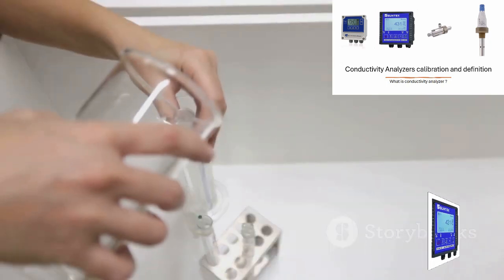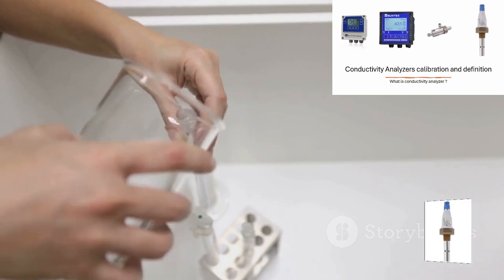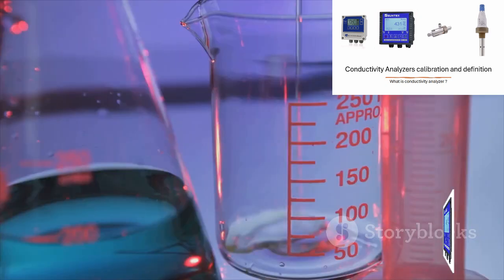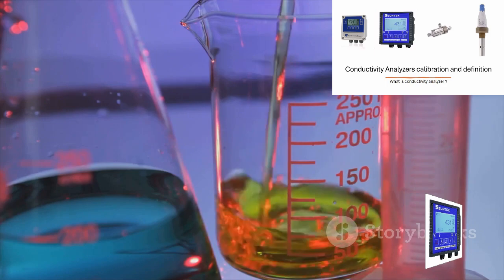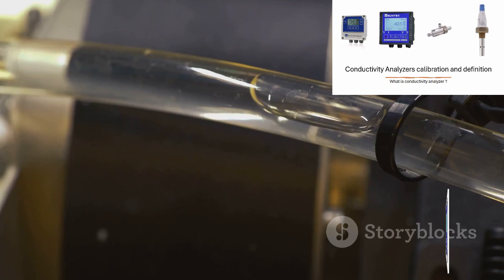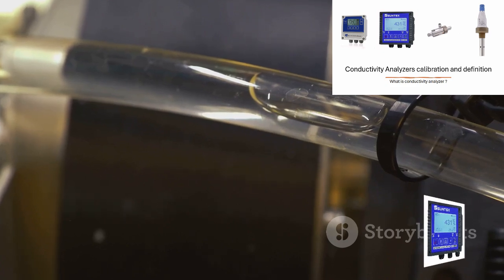Next, it's time to introduce the sensor to our standard solution. Pour a small amount of your chosen standard into a new clean beaker. It's good practice to pour just enough to cover the sensor's electrodes completely. Place the sensor into the standard solution and give it a gentle swirl to dislodge any tiny air bubbles that might be clinging to the electrodes. Air bubbles can interfere with the reading, so we want them gone.